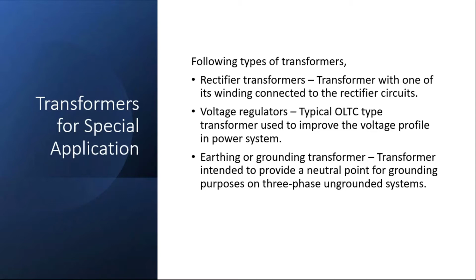In these, IEEE defines the various types of duties for these transformers, such as heavy traction and extra heavy traction, and we will go through those details in the webinar. The second application, which is very common in the utility market, is voltage regulators. As the name says, they regulate the voltage. They don't have stepping up or stepping down capabilities, but regulate only within plus or minus 10% of the input voltage. A lot of utilities that do not have transformers with load tap changers use this as a common practice to give the consumer the right voltage they need.